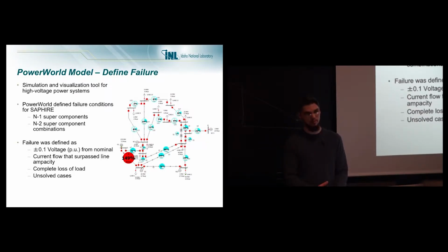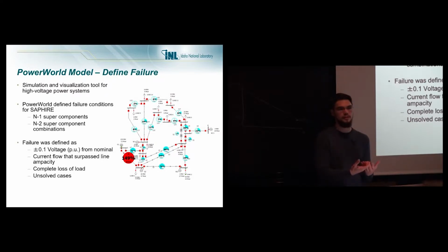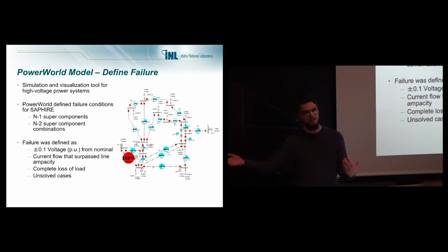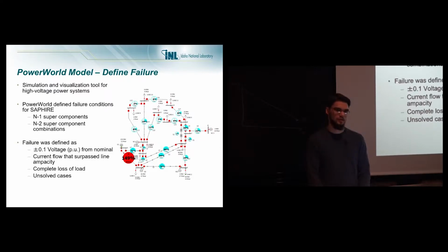So we looked at N-1 and N-2, groupings of 2 and 3 components, and stopped there because the more components you add to your failure cut sets, the less likely they are. If you have a 10% chance a component fails, needing 2 to fail at once puts you at 1%, needing 3 puts you at 0.1%, and so on. On top of that, computational time increases exponentially as we increase the number of component cut sets to evaluate. So DOE's Office of Electricity said 2 and 3 is enough for these large systems, and beyond that, maintenance is likely to handle any remaining failures.